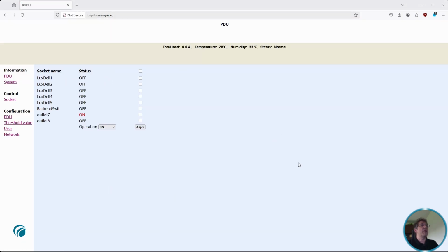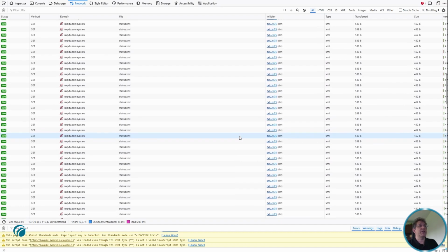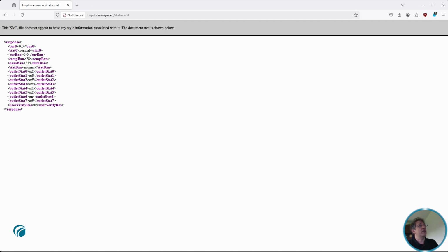Now let's return to the main page and see what happens in the networking tab. We can clearly see there's a script running called PDU.js, and instead of updating each page, it's calling status.xml. Let's look at status.xml - we see the current load, a normal status, a temperature banner, something like that, a humidity banner, and again a status banner, and there's not really a difference between status 0 and the status banner.